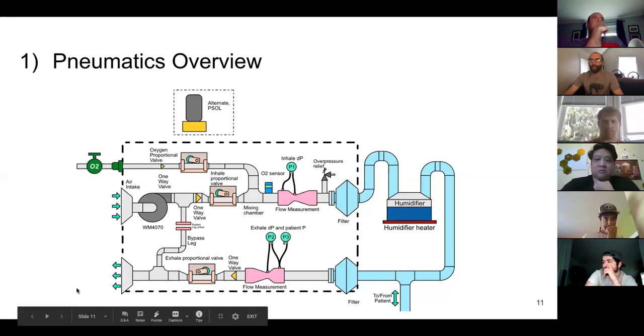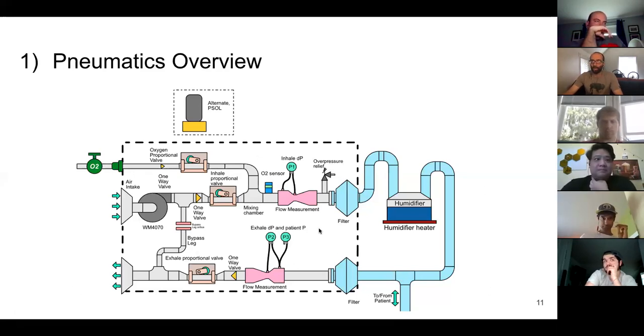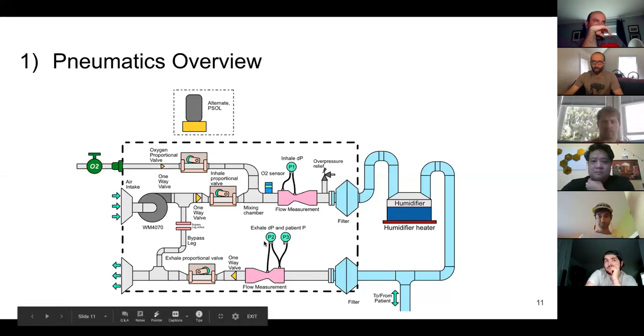And then coming back on the expiratory limb, these are again in the box: patient side filtration, patient flow measurement, check valve, and then the exhale proportional valve.